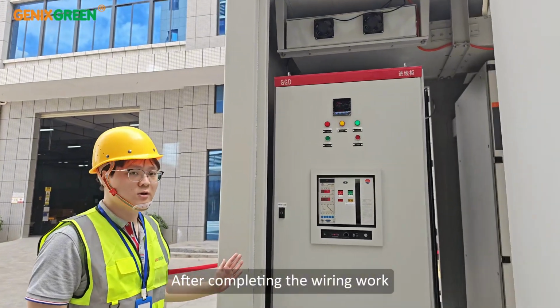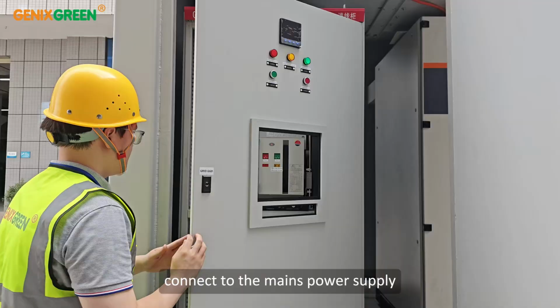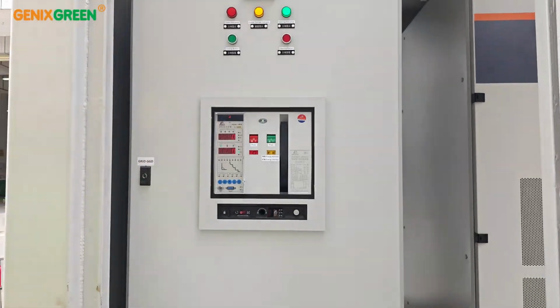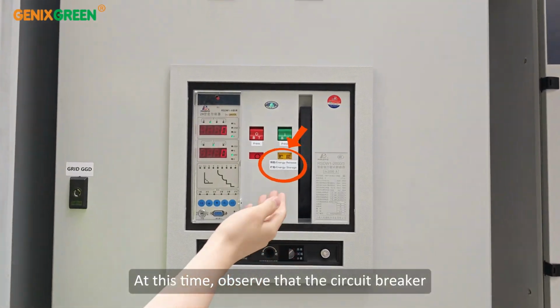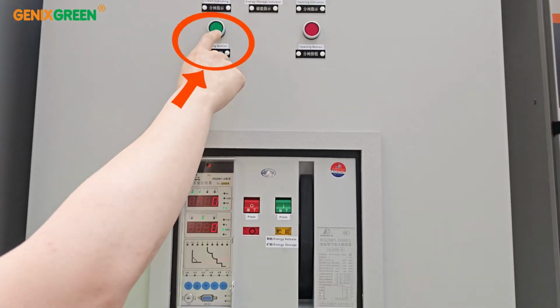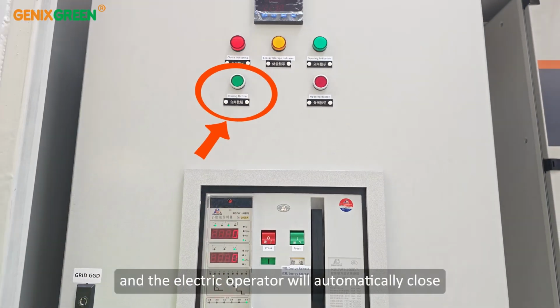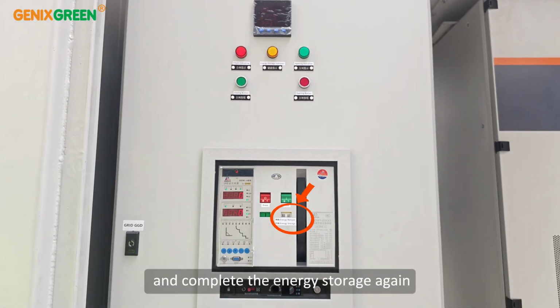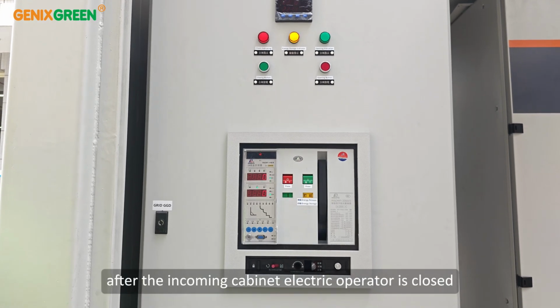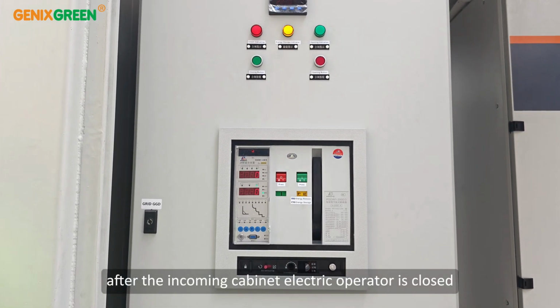After completing the wiring work according to the installation manual, connect to the mains power supply. At this time, observe that the circuit breaker is in the energy storage state. Click the closing button, and the electric operator will automatically close and complete the energy storage again. After the incoming cabinet electric operator is closed, close the compartment door.